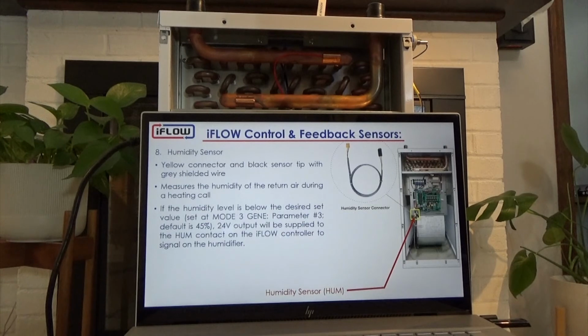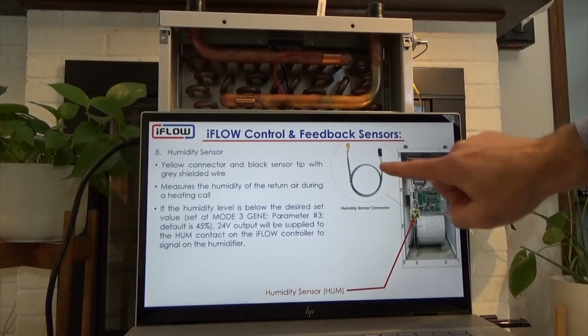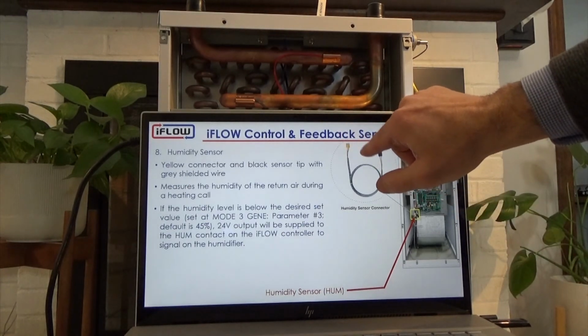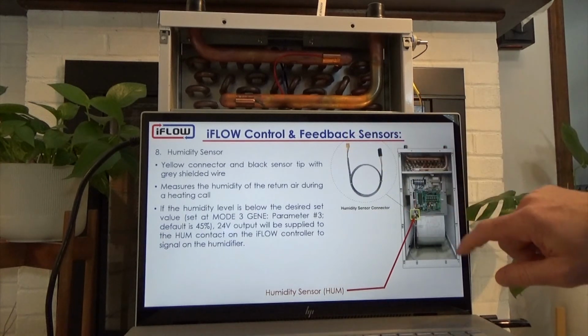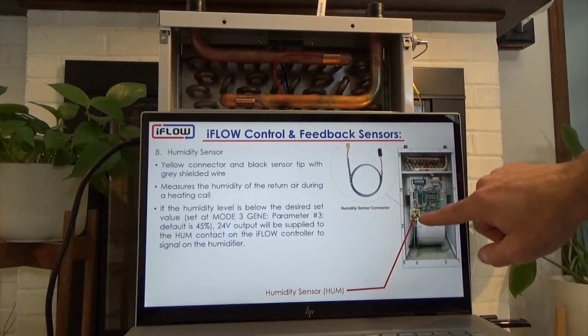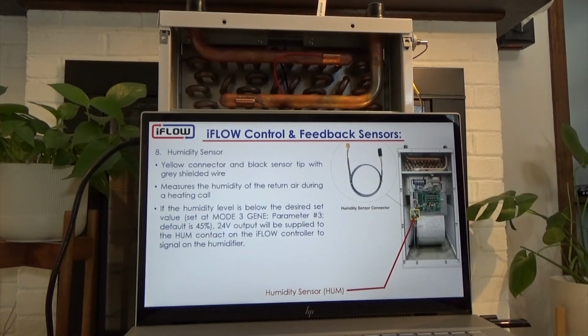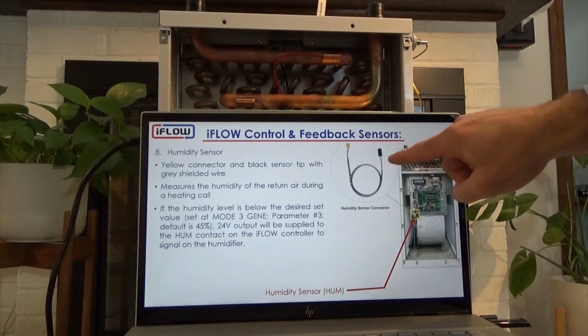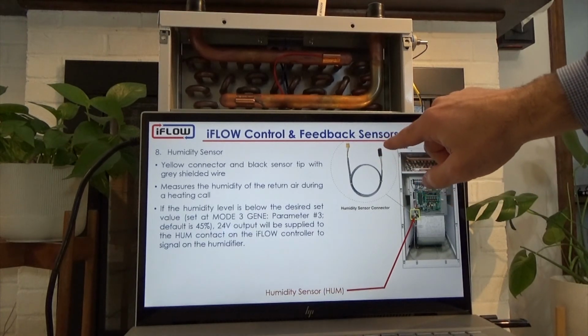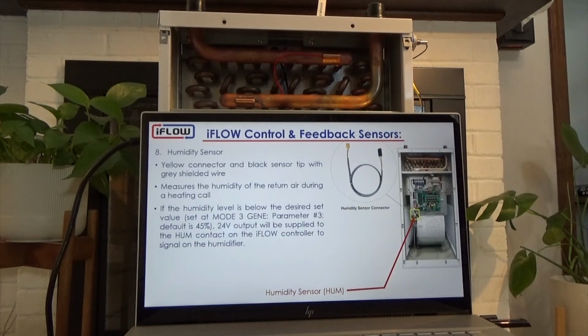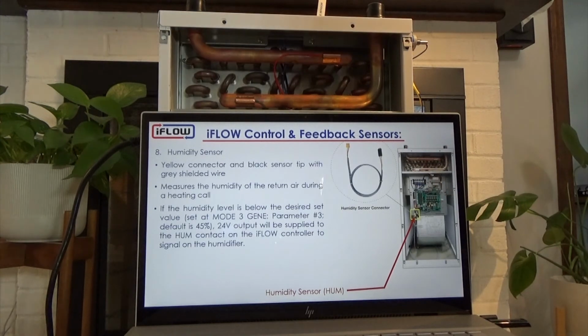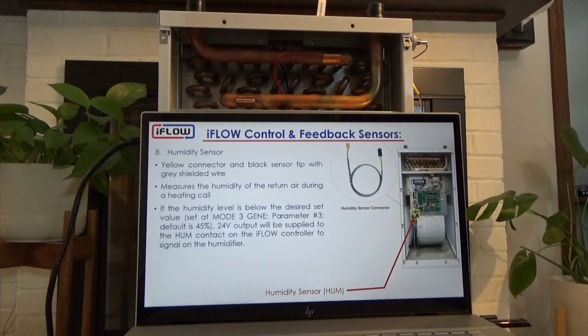The next is the humidity sensor. So the humidity sensor has a yellow, kind of a dark yellow connector. It connects again to the wiring harness just below the lower left corner of the board, kind of just above the blower. And then the wiring harness, or the sensor itself, is the black end, and that will detect the humidity of the return air.